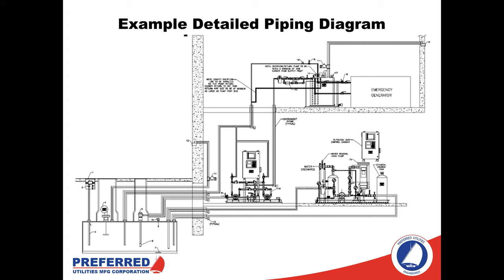Following the fuel as it moves throughout the system, we next have our duplex transfer fuel oil skid with two transfer pumps — very typical for mission-critical applications, where one pump is sized for the full function of the system and the other is a lag or backup pump. Following the fuel from here, it goes up to the generator, filling a day tank or local storage tank at the generator itself. We're going to take a closer look at each part of this system and how we would size each component, as well as the piping and valving.